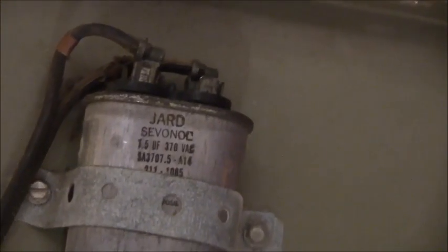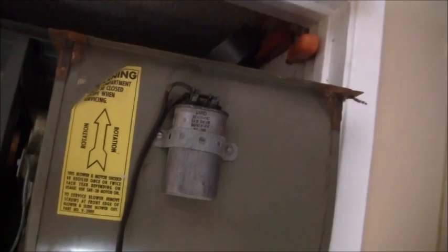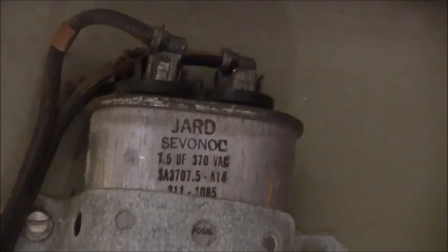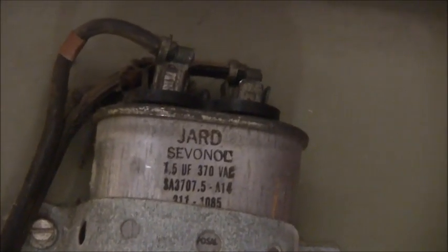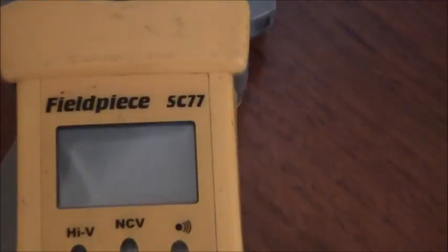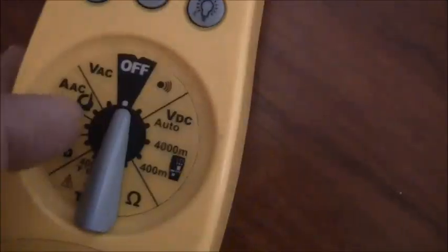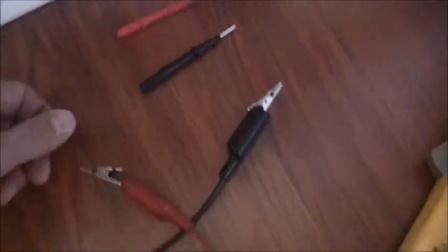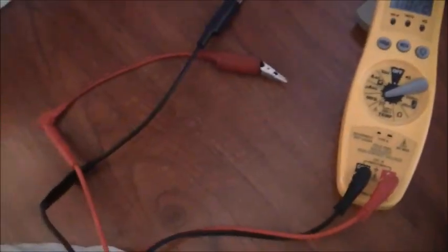It looks like that is 7.5 microfarads. Let's throw my meter on it. The camera loses focus when I get in tight, but that's the best I can get. For my meter, I've got a Fieldpiece SC77. You put your meter on microfarads right there. I think I got this meter for like $200. I switched out my leads from the standard terminals and put on alligator clips so I don't have to hold two things simultaneously.